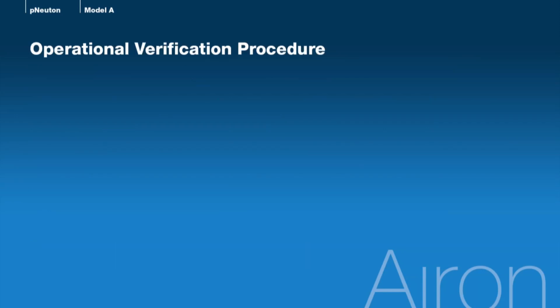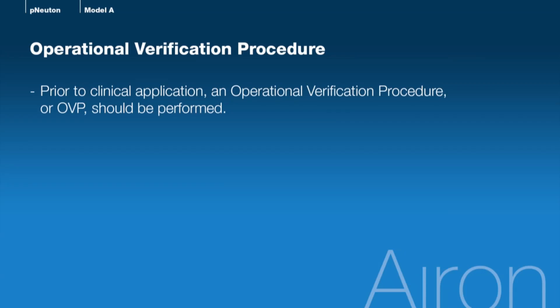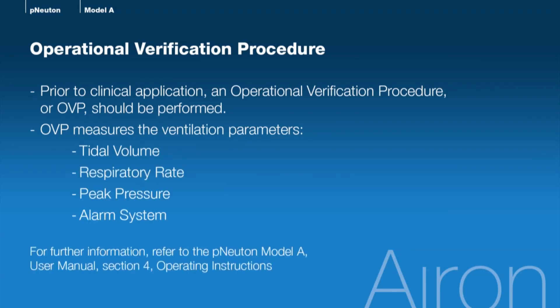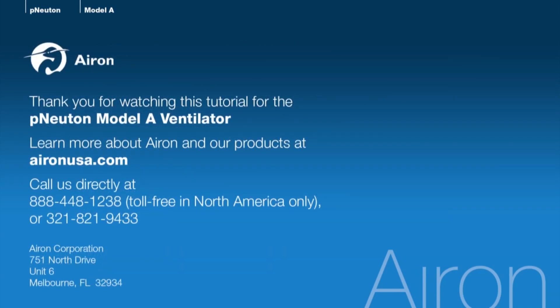One last step. Prior to clinical application of the pNeuton Model A ventilator, an operational verification procedure or OVP should be performed to validate the device's performance to specifications. The OVP will measure the following ventilation parameters: tidal volume, respiratory rate and peak pressure, and the alarm system. For further information, please refer to the User Manual, Section 4, Operating Instructions. Thank you for your time today. This concludes our pNeuton Model A ventilator in-service tutorial. For further information, feel free to visit us at aironusa.com or call us at 888-448-1238.